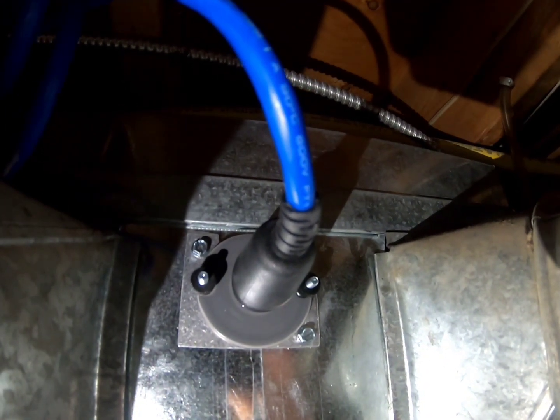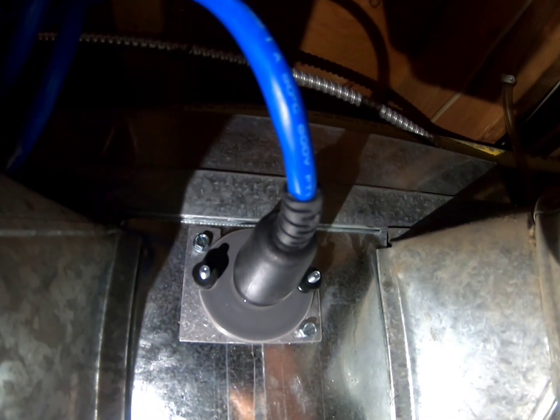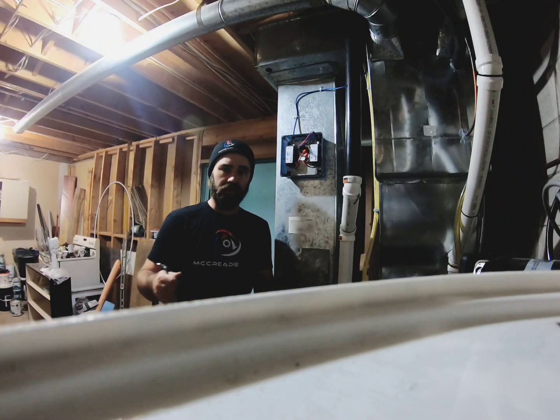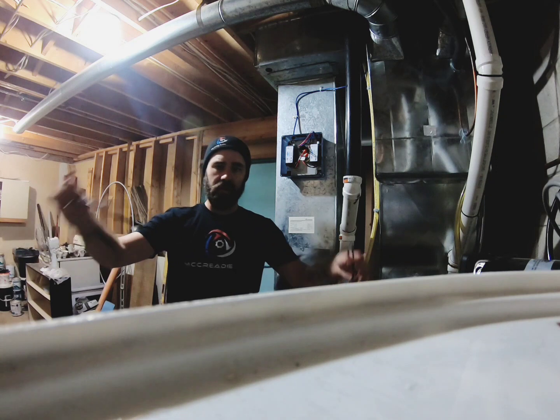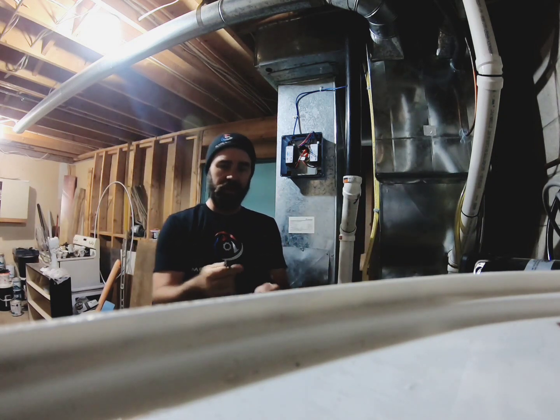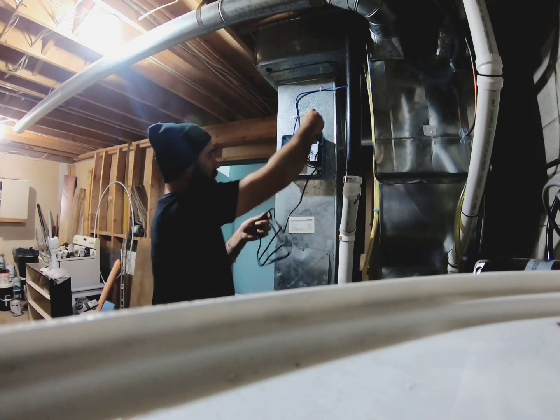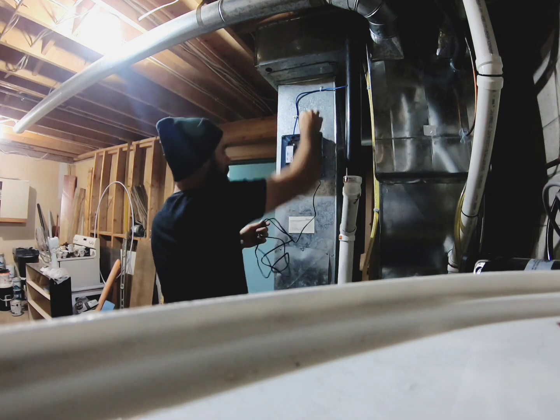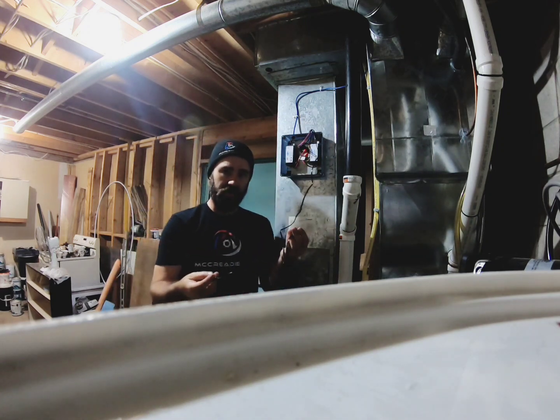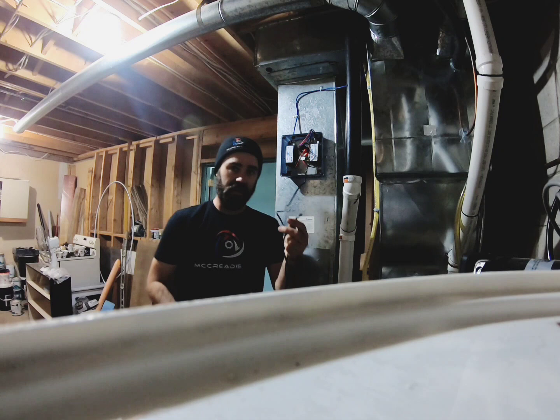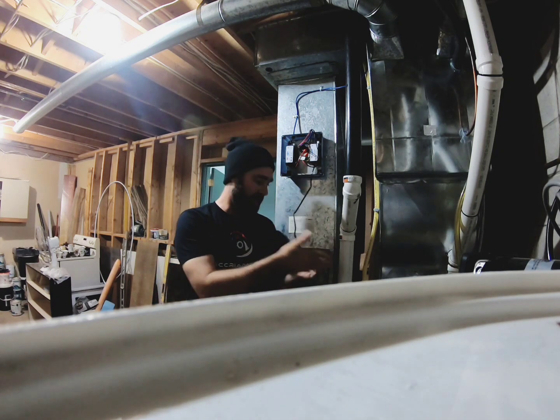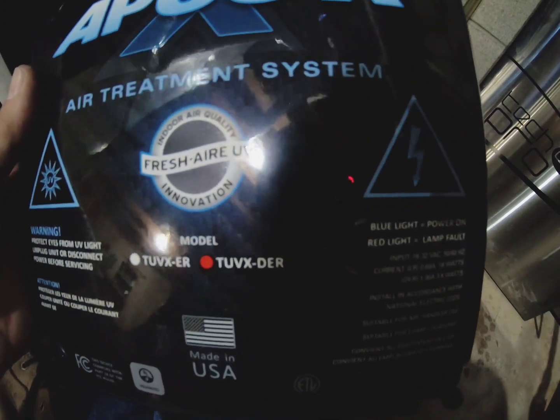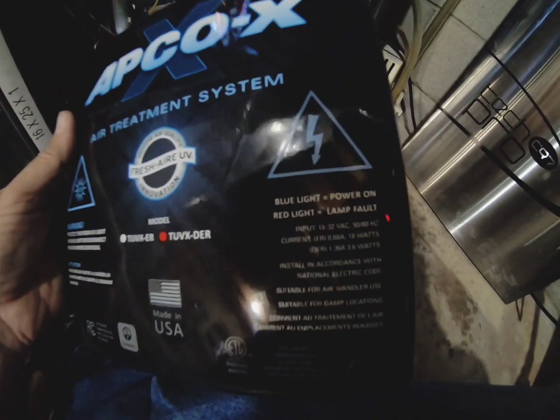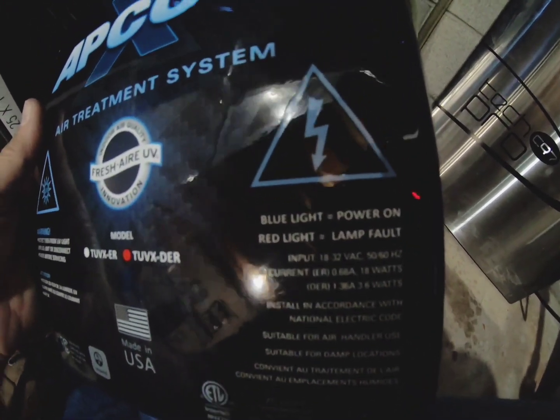Now we have to power the APCO-X up with 24 volts. So this is a 24 volt installation, and the unit comes with this power cord. In one end we have a connection point that plugs into the top right here, and then we can route our wire down into the air handler or furnace and pick up the 24 volts needed to power up the APCO-X. So here's the nameplate here. We are using the TUVX-DER, and it draws approximately 1.36 amps.